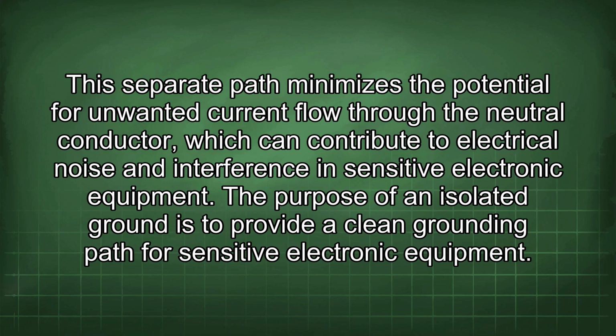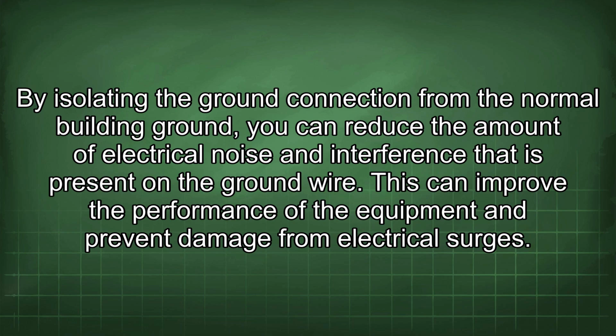The purpose of an isolated ground is to provide a clean grounding path for sensitive electronic equipment. By isolating the ground connection from the normal building ground, you can reduce the amount of electrical noise and interference that is present on the ground wire. This can improve the performance of the equipment and prevent damage from electrical surges.